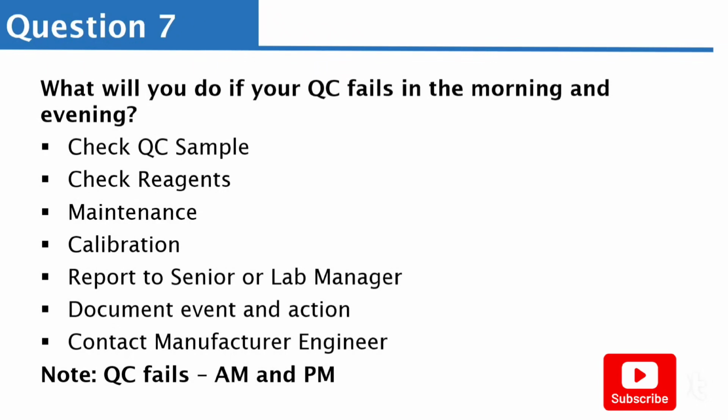There is a possibility that something is affecting it, maybe something is happening with the analyzer itself. Or it can also be due to a certain reagent, maybe if they are very sensitive, as the case may be. But in most cases, you might need to make sure the analyzer is checked, and maybe you call the engineer to look at it and find out if there is anything that is actually affecting the QC.